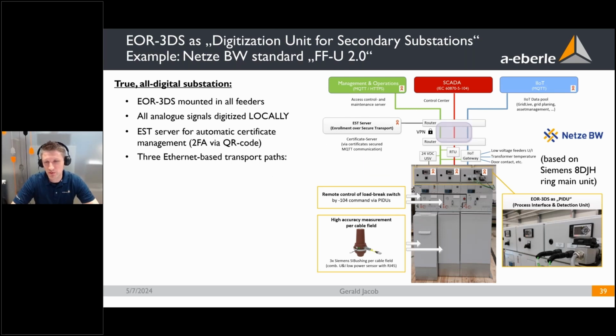So now we come to the concept itself regarding our devices and the compact switchgear station. This is not the complete digital secondary substation. As I mentioned, there's also a low voltage side that is not shown here. We focus now on the medium voltage part of this digital secondary substation, and especially here regarding our earth fault indicators. So this type is a real, true, all-digital secondary substation, where really no serial protocol is used at all. There are other DSOs that are using Modbus RTU internally inside the secondary substation, not so with the standard of Netze BW. Every device is connected directly in a digital manner via Ethernet, and all analog signals are digitized locally, directly in the respective feeder.